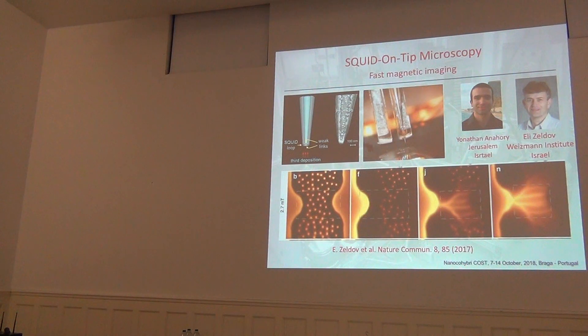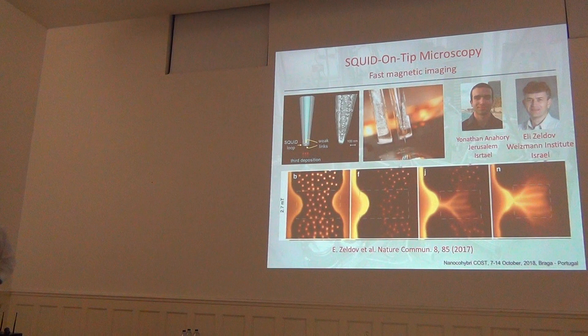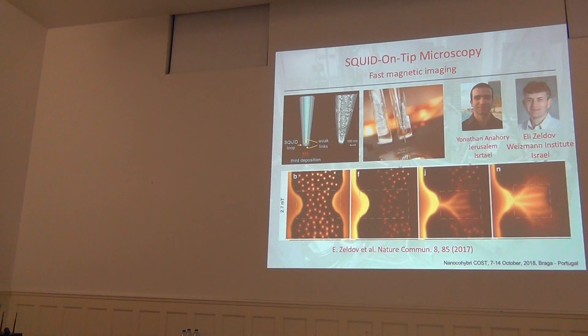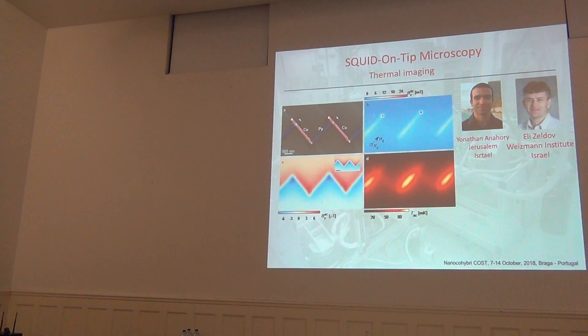To be safe, for instance, you can do it as the following: you can land on one position, second, third, and fourth that limits your image, then you construct by computer a plane which corresponds to your zone, then you make a lift, let's say, few tens of nanometers to be safe, and then you can scan very fast without a danger to crush your so dear device.